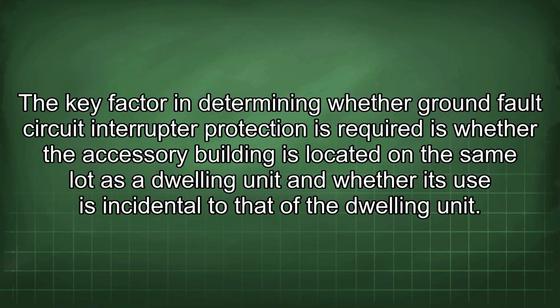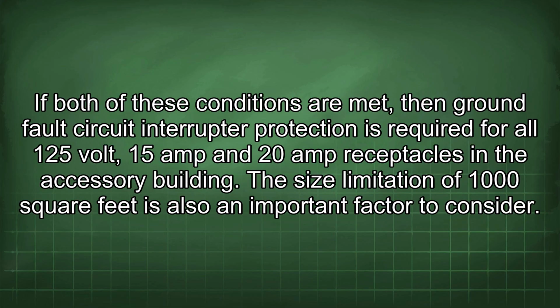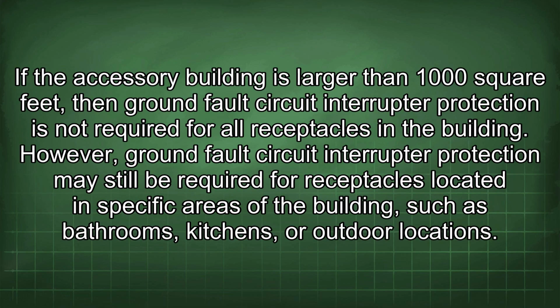The key factor in determining whether ground fault circuit interrupter protection is required is whether the accessory building is located on the same lot as a dwelling unit and whether its use is incidental to that of the dwelling unit. If both of these conditions are met, then ground fault circuit interrupter protection is required for all 125 volt, 15 amp and 20 amp receptacles in the accessory building. The size limitation of 1,000 square feet is also an important factor to consider. If the accessory building is larger than 1,000 square feet, then ground fault circuit interrupter protection is not required for all receptacles in the building.